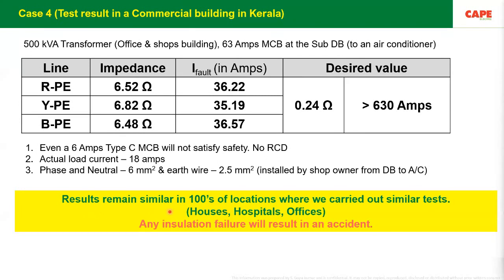And out of this, the results, actually similar result of this shop, it is remaining in hundreds of locations across India. I would say about more than 90 to 92% of our installations, the earth fault protective measures are similar. Means there is no safety at all. It is common in houses, hospitals, and offices. Any insulation failure will result in an accident.